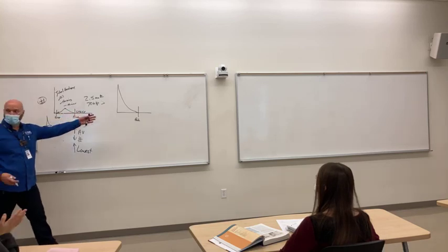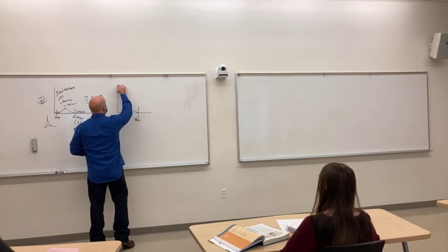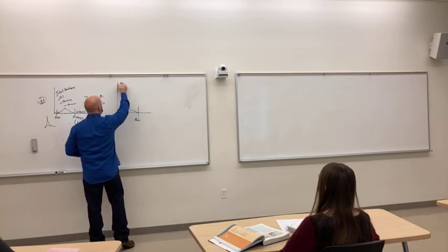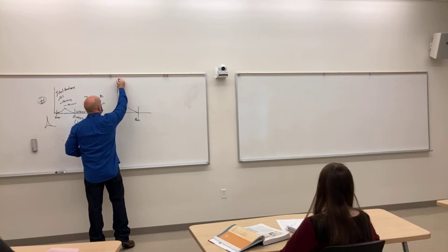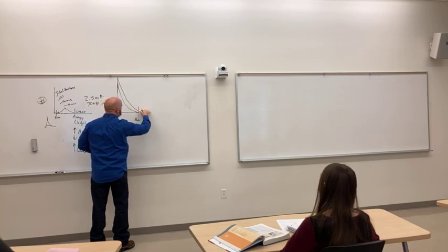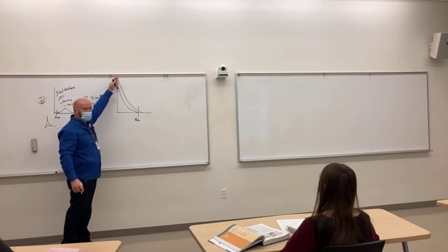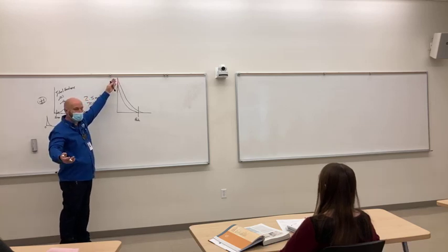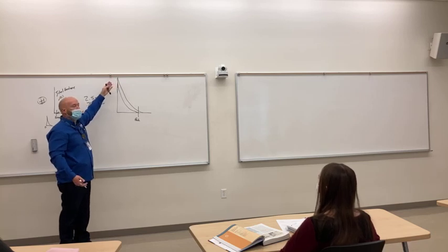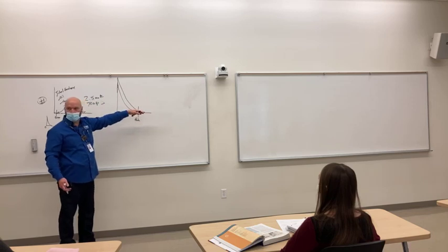To the right, right? So if I were to change nothing but my kVp, or remove filtration and change nothing but the kVp, my spectrum should be fairly parallel to that one. It's going to start higher. I'm going to create more X-rays. Most of those X-rays are going to be low energy photons, for the same reasons they were low energy photons before, but I'm going to get more of them, okay?